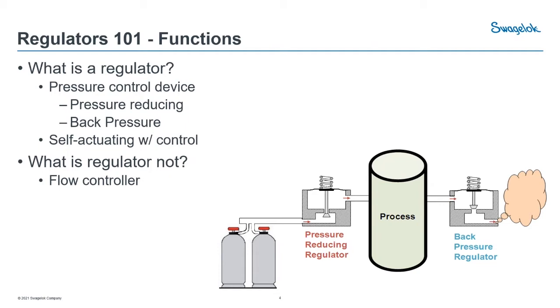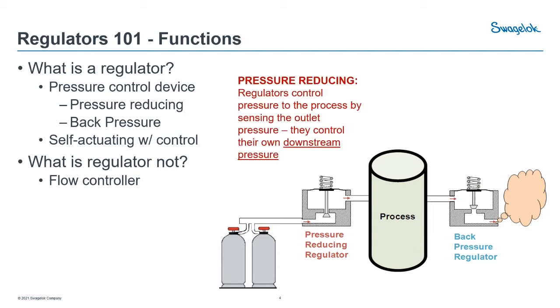These are what I tend to call self-actuating with control, because you're going to be able to dial that handle down to set the pressure that you want. From there, the regulator will self-actuate and control the pressure you had set. Looking at the picture on the right, in our processes we generally see these two models: before the process, pressure reducing regulators control the downstream pressure, and after the process, back pressure regulators control the upstream pressure.